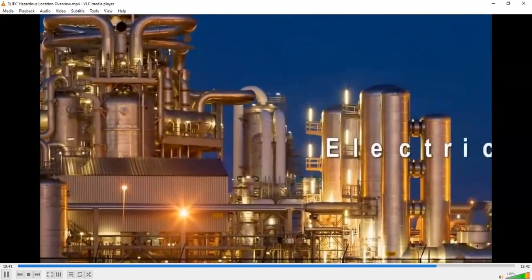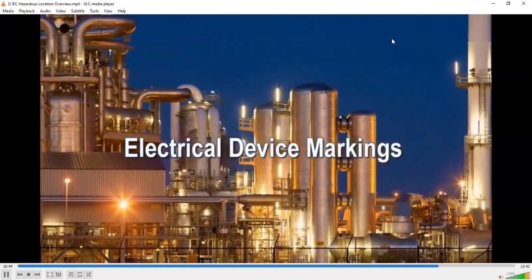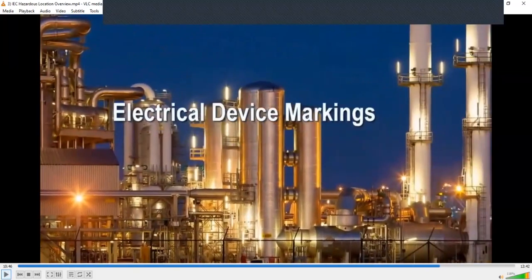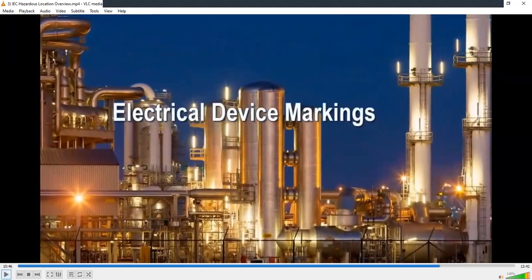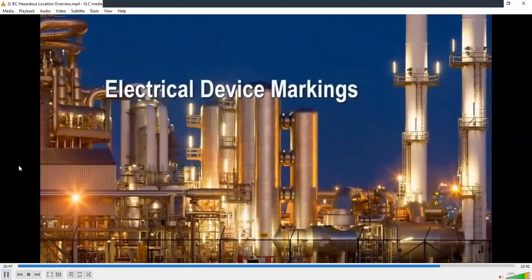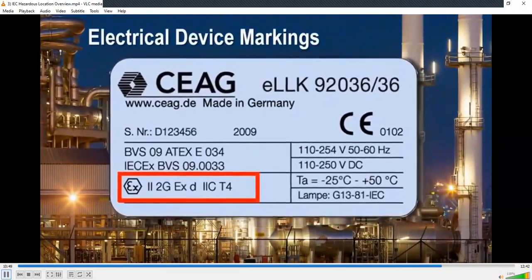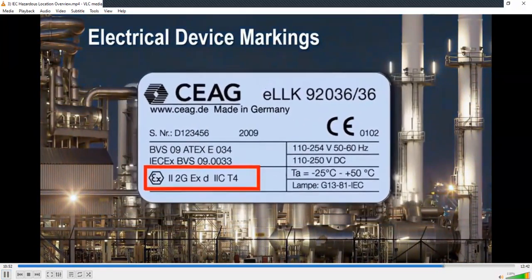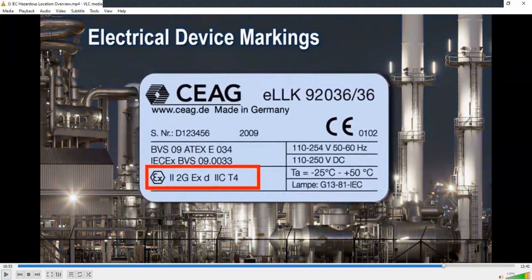All equipment certified for use in hazardous areas must be labeled to show the type and level of protection applied. Okay, so here they will be showing on a motor. Pay particular attention to this. Those are the markings that I mentioned, safety markings with regard to electrical fittings within the hazardous region. In this example, we will review a fluorescent light fixture for a hazardous environment. The examiner might give you something like this. Okay, so he'll ask me what each one means. Just pay attention to this.